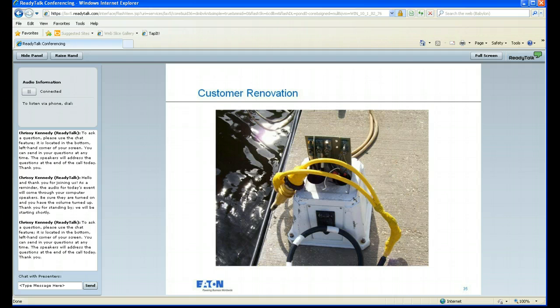This is an example of a typical customer renovation that we see. This person has basically tied their both side electrical cord right into a bus bar system on a power pedestal. Likely caused by somebody running over the unit, but still this is potentially dangerous on a ton of different levels. Not only is there no circuit breaker protection present anywhere on this unit, the bus bar system that I'm going to circle right here, those are live connections.